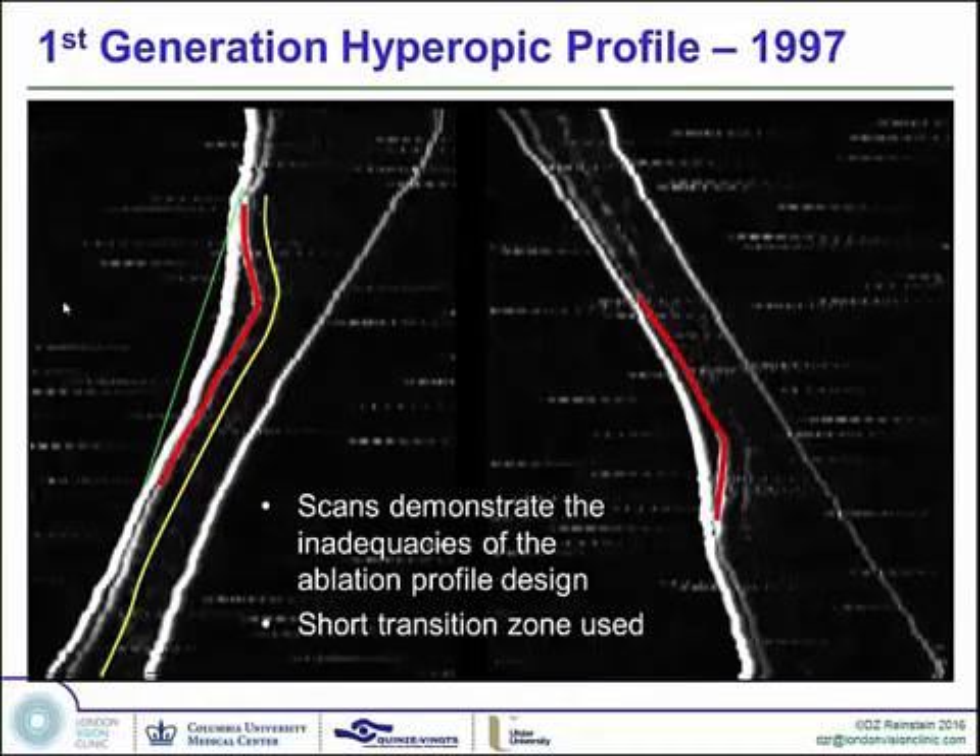About half or more than half of the thinning in the mid-periphery was compensated for by epithelial filling of that groove. This was due to the fact that the Nidek had very inadequate transitions — you can see the ablation profile exits very quickly from the deepest point. Many other lasers were also being programmed with these small optical zone, small transition zone treatments.